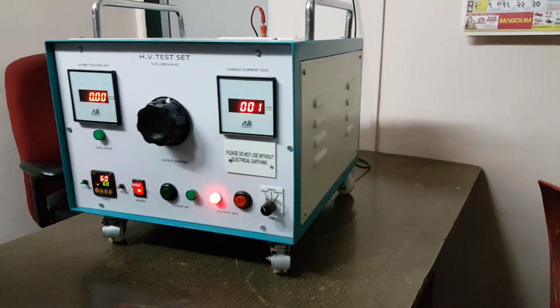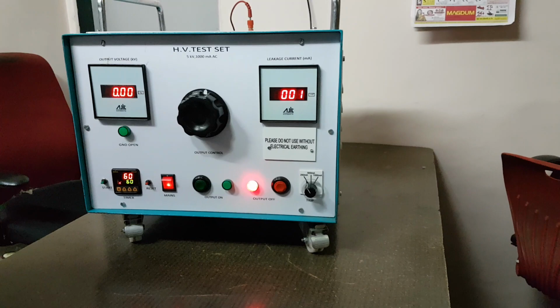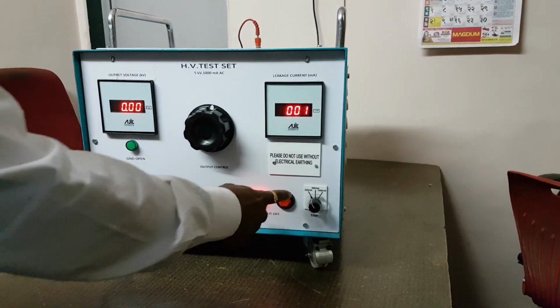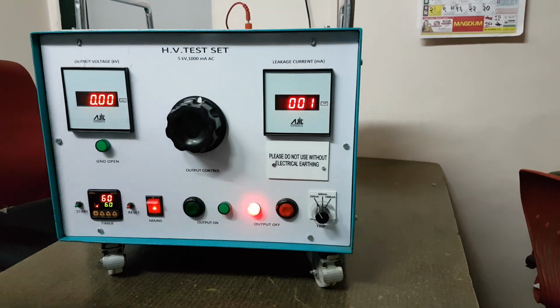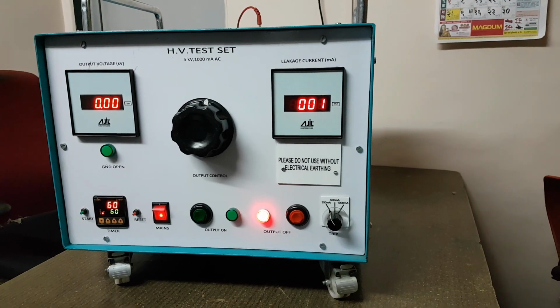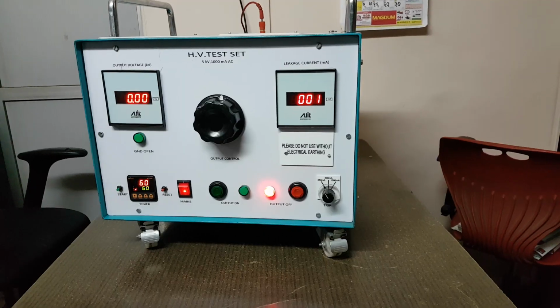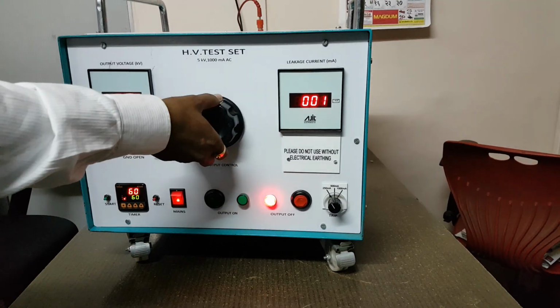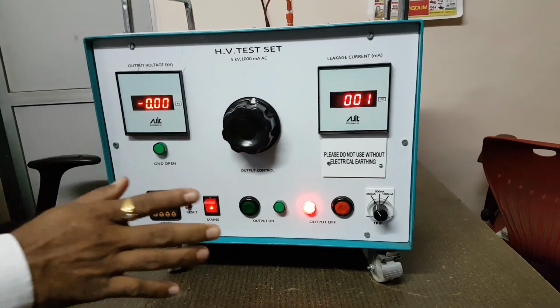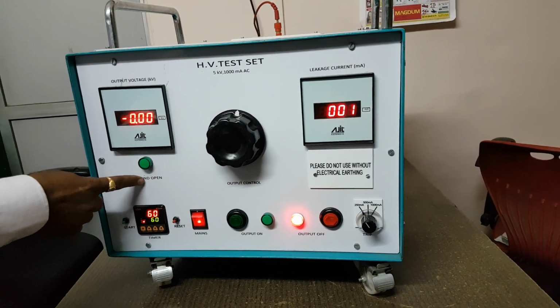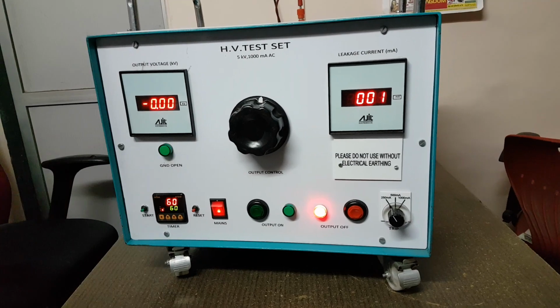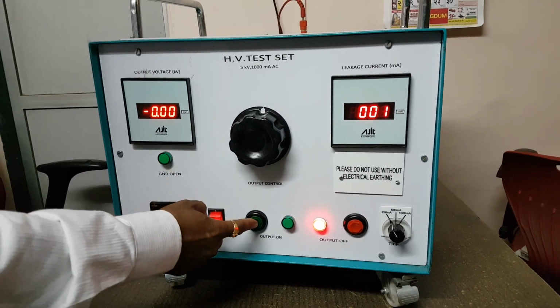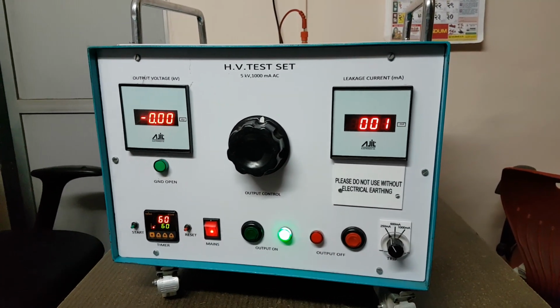Okay, this means the output is shorted, and if this shorting current or the short circuit current or the output current exceeds this 250 milliamperes, then the output is automatically tripped off. Okay, now let's see. Now I am at 0, so 0 interlock is operated properly. Now ground is also connected properly. Now I can initiate the high voltage.